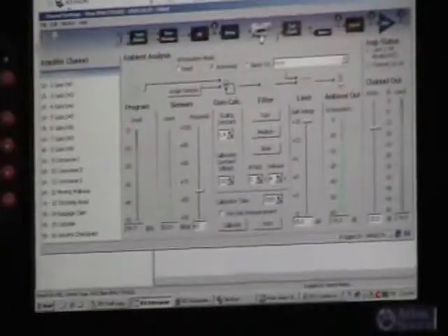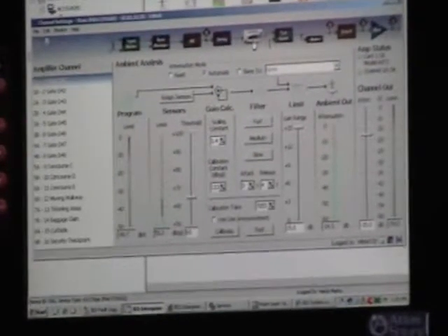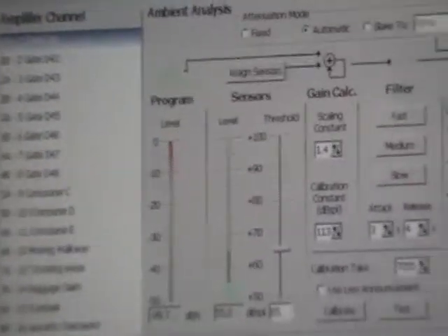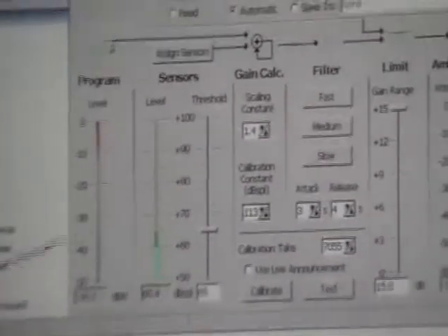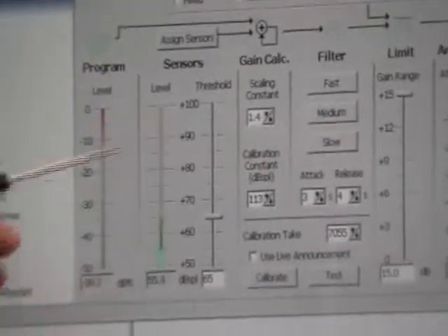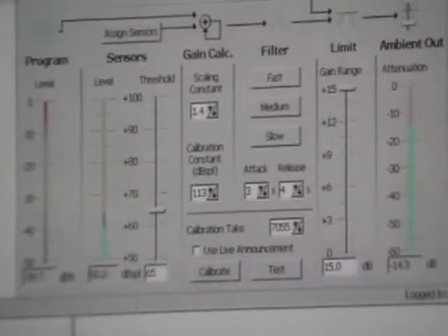The ambient noise channel looks like this, and that's the signal going through there. And I've actually got this channel in automatic, and I haven't demonstrated that because it's probably turning up and down on me. But here's test points, meters, the D to A coming out, and the amp, and these are all monitor points. If you had a monitor speaker, you could monitor all the different sections of that. And this shows the level and all going through the system. And you can see this level here changing. That's with me talking, that's its sensor. So that's the Titan series, how that works.